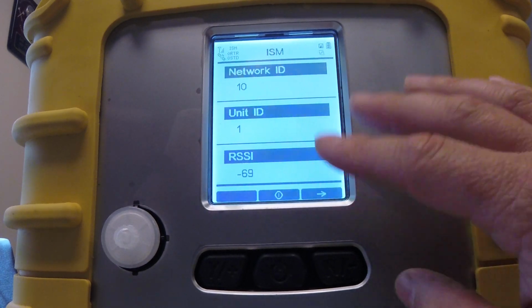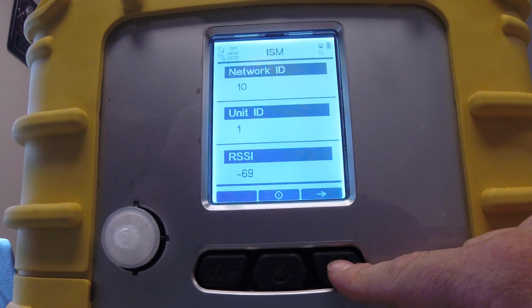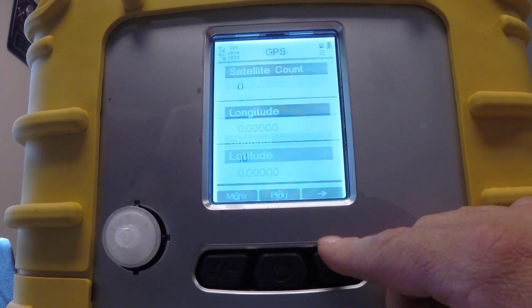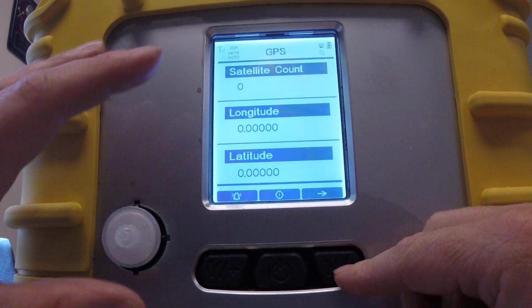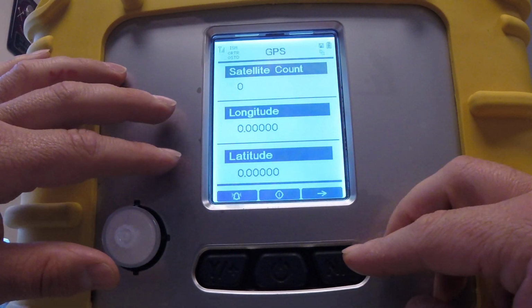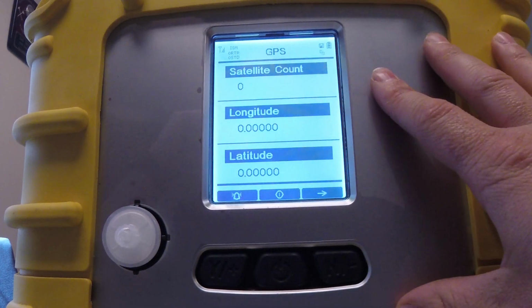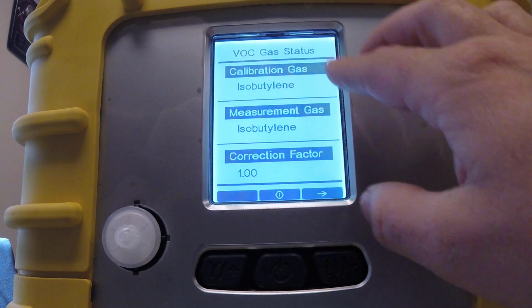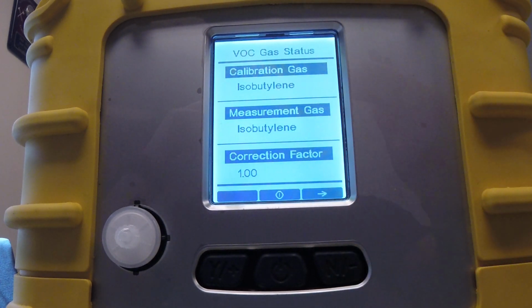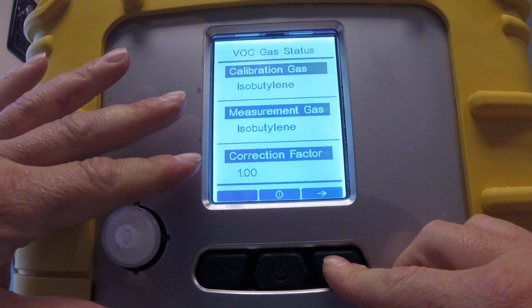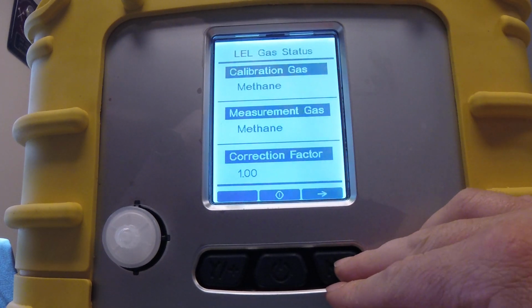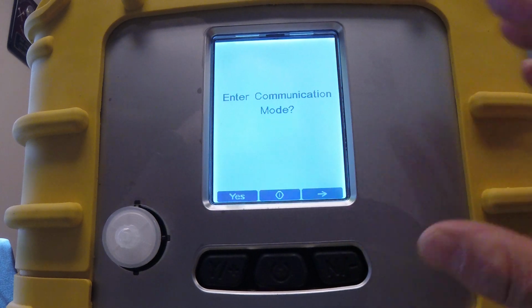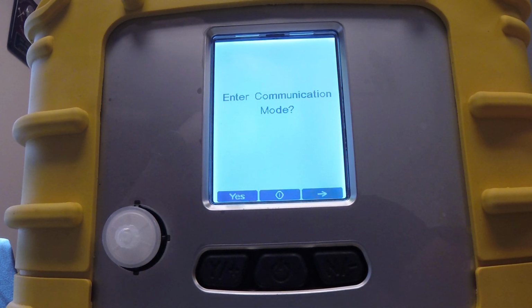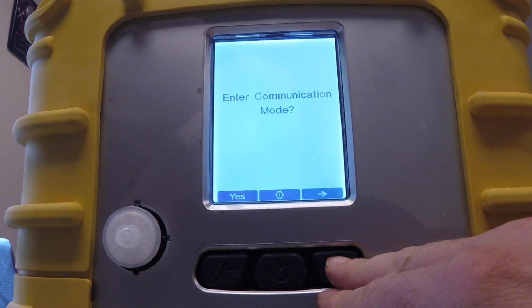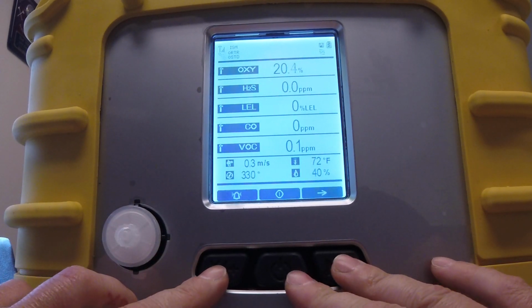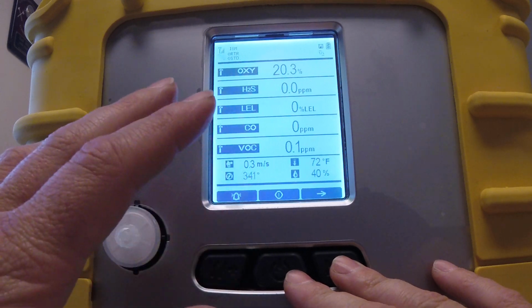Network unit, these all come into play with ProRAE Guardian and communicating with the other instruments. They all need to read the same with the channel and the PAN ID. All those things should already be set up, so we're not going to worry about those. This will show your satellite count and then a relatively accurate latitude and longitude for the AreaRAE. For our volatile organic compound, it's our calibration gas and measurement gas with a correction factor of 1, so we can go in and change all these things if we need to, which we don't. Same with the LELs, calibrated off methane, which is the same with all of our other instruments. So communication mode is to basically hardline into the computer and pull data off of the instrument and adjust settings as we need to. So that's how loud your alarm is, so it's pretty amazing.